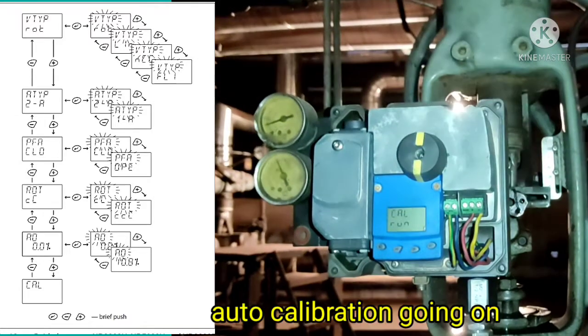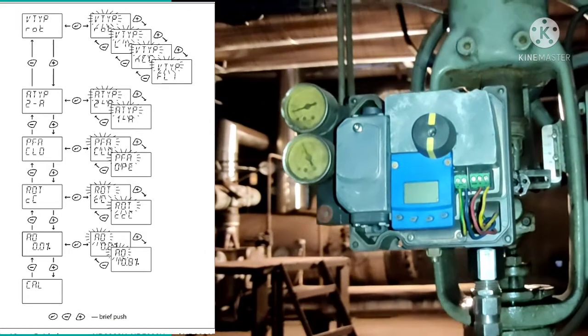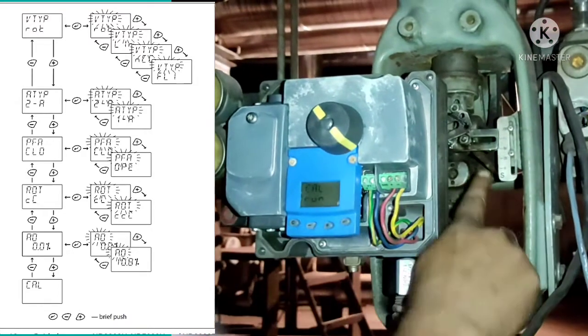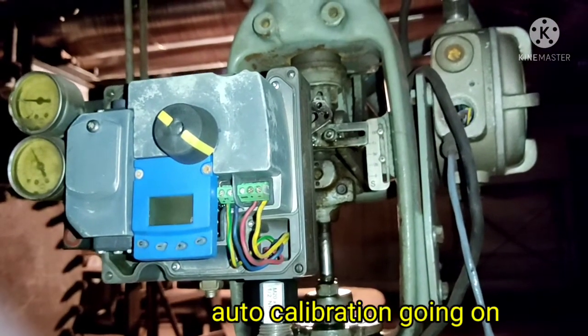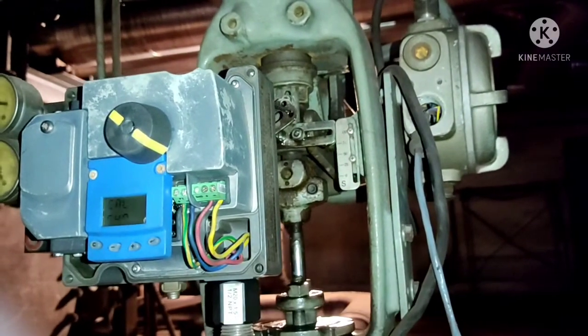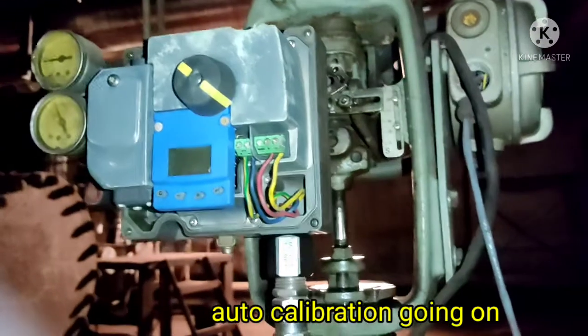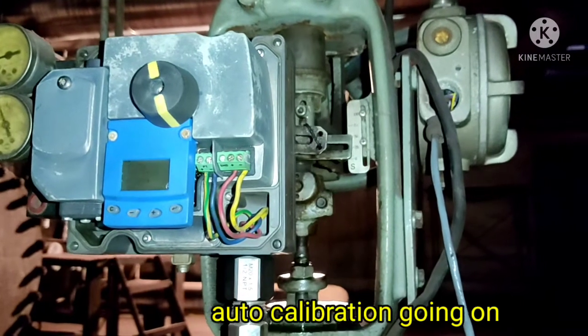The actuator of the valve gradually moves during calibration — it takes several minutes, almost 5 minutes. In the display, CAL run is continuously blinking. We are also watching the actuator of the control valve continuously going up and down. This up and down movement is continuously checked by the positioner in auto calibration mode.